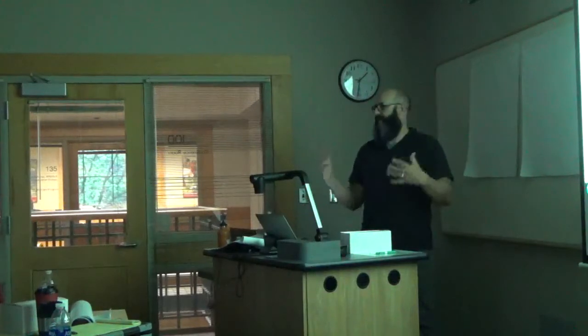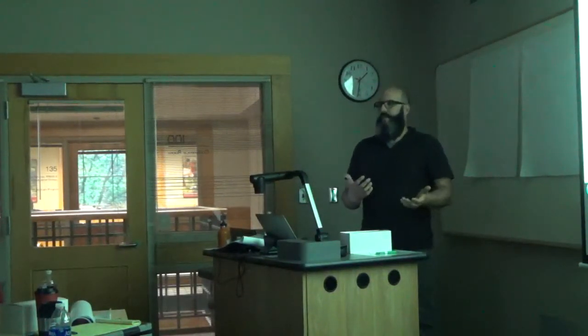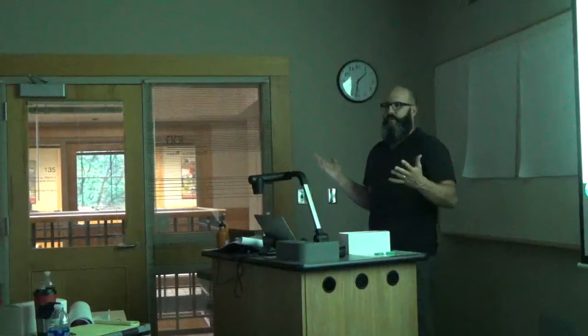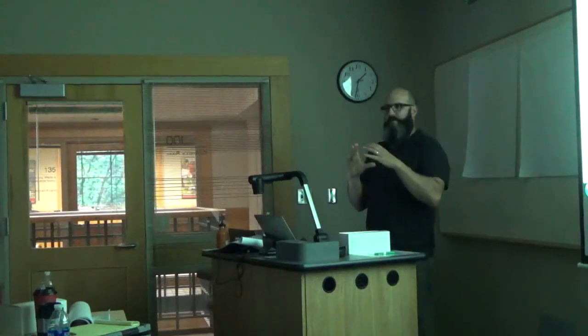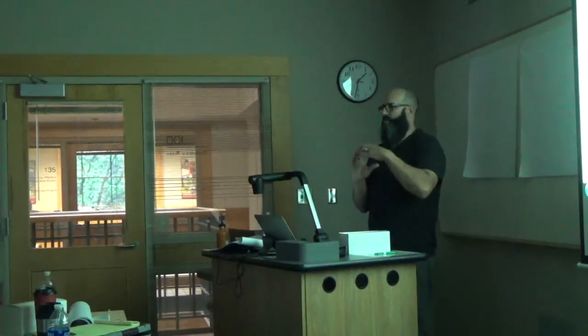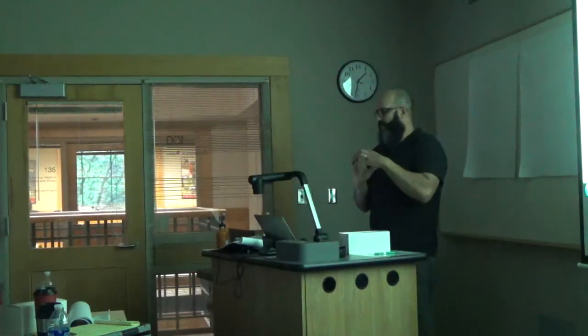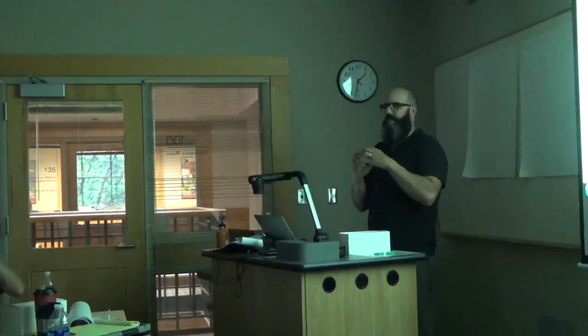We're also running on these houses a different ventilation strategy. We're not running fans to all the bathrooms. We're running a central ventilation system with a high-low heat exchange and energy recovery, and we also have the dryer and the cooktop requiring mechanical heated makeup air. And so we now have a makeup air unit. And this is something that isn't in most houses at all, because makeup air is sort of leaked in through building leakage and is diffused through the whole building, as opposed to now bringing this air in through a very small opening and trying to dump it somewhere in the house, where when you concentrate makeup air anywhere in the house, if it's cold out, it's going to cause problems. So the design of the system is really important. The understanding of how a mechanical system works is really important, and then making sure we execute.